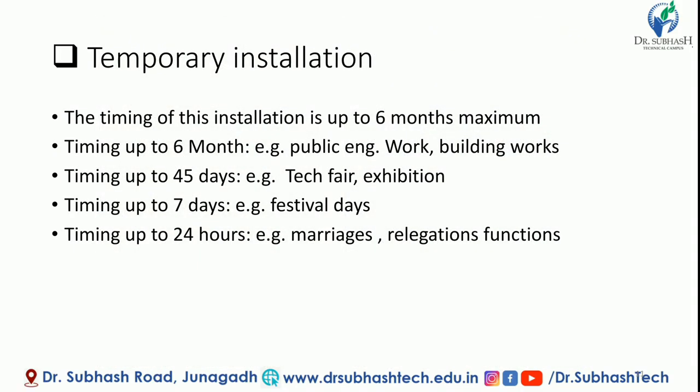Temporary installation has a maximum duration of up to six months. Beyond six months, it may not be called temporary installation. Examples include public engineering work and building work. Installation up to 45 days is for technical fairs and exhibitions. Festival days use temporary installation for about seven days. Installation up to 24 hours includes marriage functions, school functions, college functions, and regulation functions. Lighting on wooden poles that is not permanent is called temporary installation.